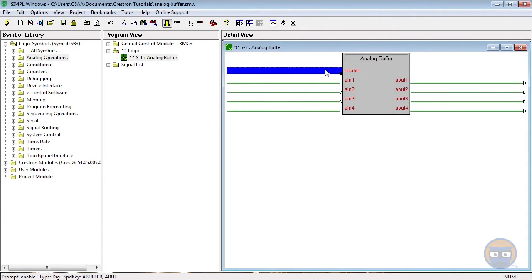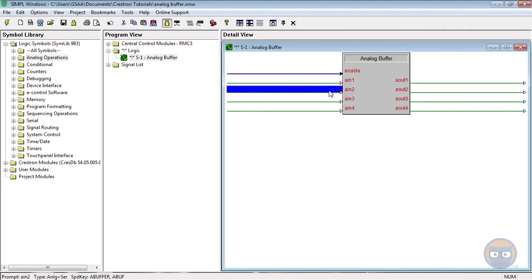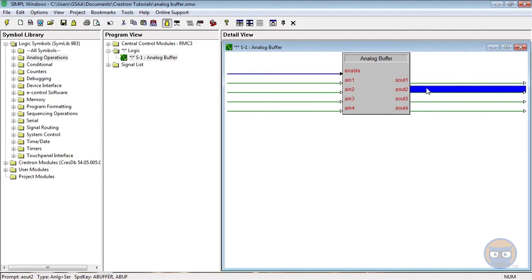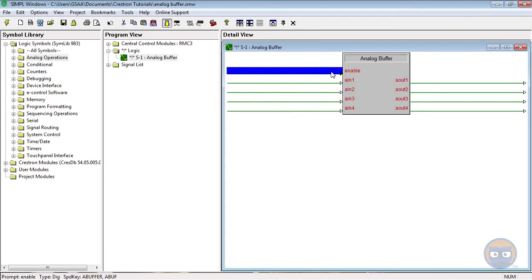For analog signals, when the enable line goes low, all analog outputs keep their previous values. When the enable line goes high, any analog inputs are resent or propagated to their outputs.